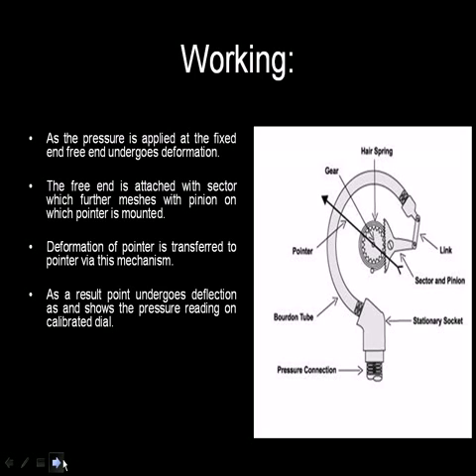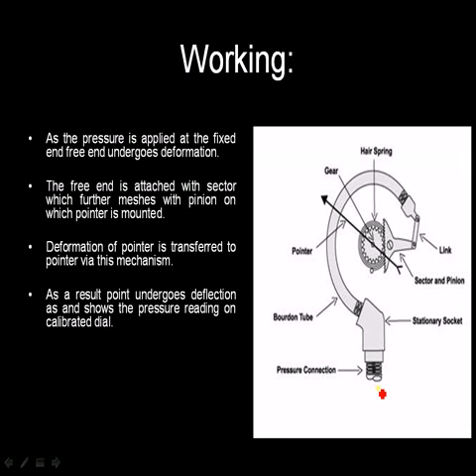Let us see its working. As the pressure is applied at the fixed end, the free end undergoes deformation. This is the fixed end where pressure will be applied. Now this end is actually a free end, but it is closed. As it is closed, the fluid pressure will act over this end.